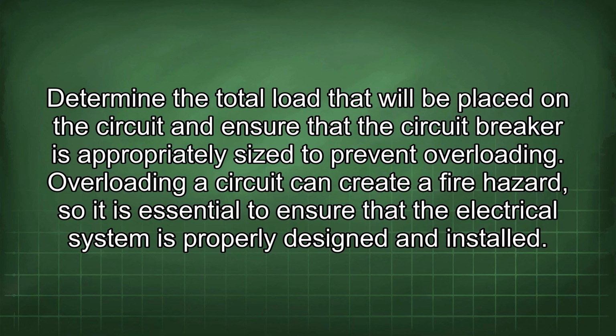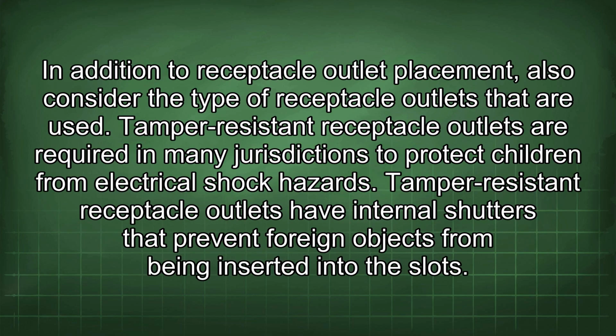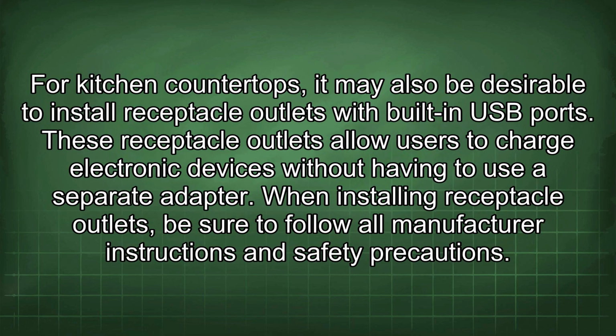designed and installed. In addition to receptacle outlet placement, also consider the type of receptacle outlets that are used. Tamper-resistant receptacle outlets are required in many jurisdictions to protect children from electrical shock hazards. Tamper-resistant receptacle outlets have internal shutters that prevent foreign objects from being inserted into the slots. For kitchen countertops, it may also be desirable to install receptacle outlets with built-in USB ports. These receptacle outlets allow users to charge electronic devices without having to use a separate adapter.